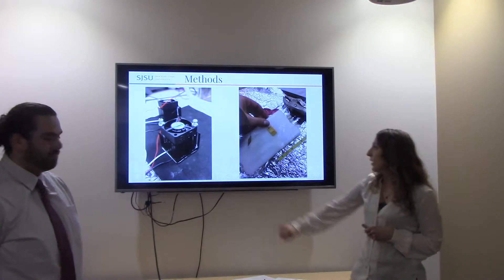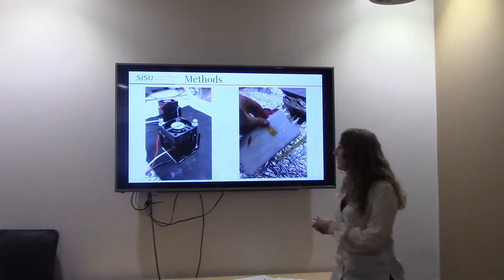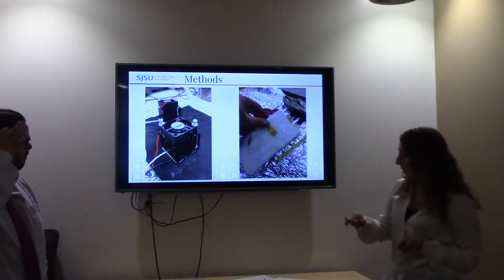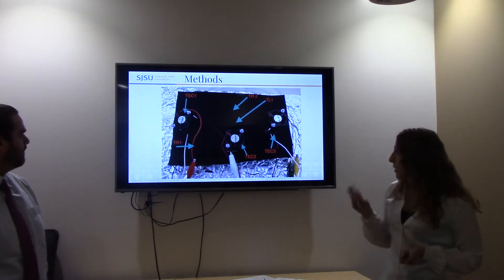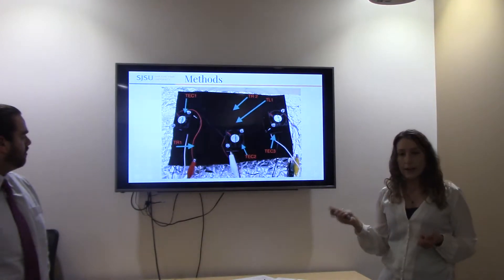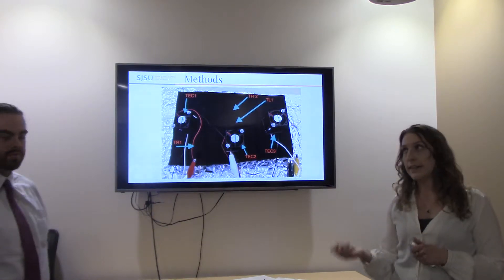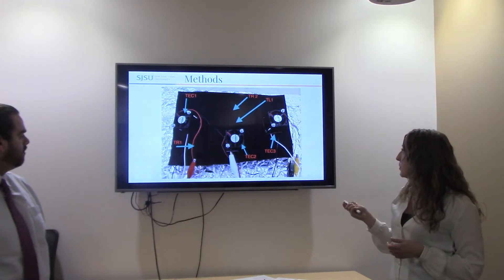In our latest model, we had the TEC on the bottom, the heat sink above it, and a fan used for active cooling, with neoprene around it. We used flat temperature sensors, which worked better than our initial ones. In our last test with three thermoelectric coolers, we were exploring what configuration would give us the best temperature distribution — ideally equal distribution across the skin surface at 18 degrees Celsius or lower — with some sensors placed directly under the TECs and others at different intermediate spots.